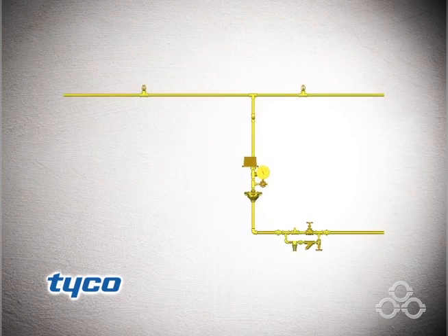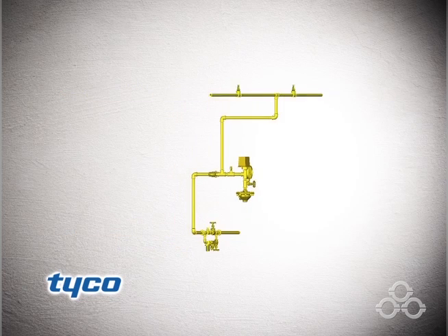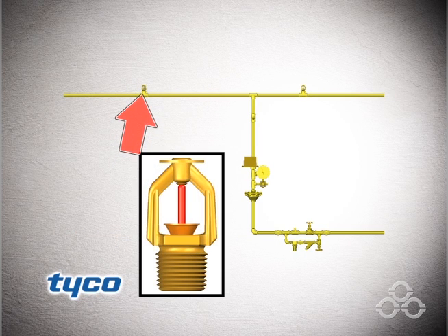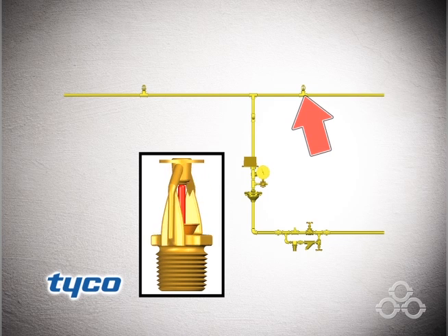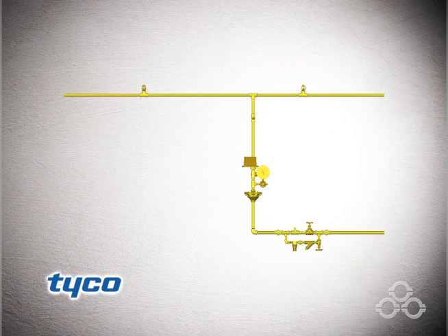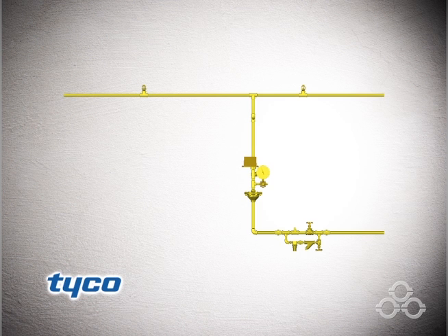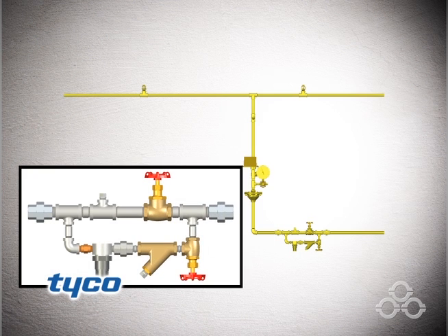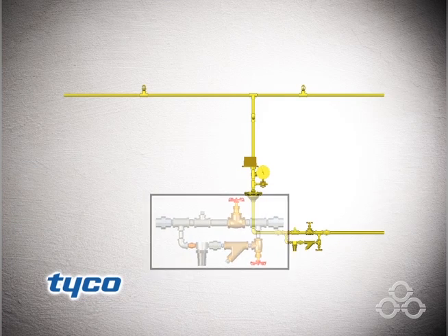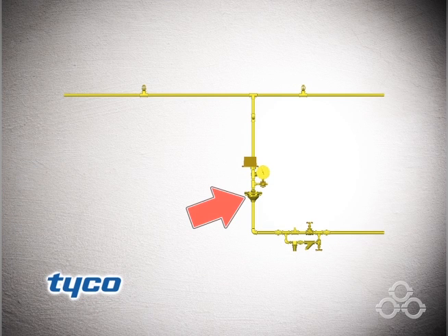The actuation system is shown here in yellow. The dry pilot actuation system is equipped with fire detection dry pilot devices, such as the Model FTR-1 fixed temperature release or automatic sprinklers. These are pressurized by air through an optional Model AMD-1 air maintenance device and the pilot port of the Model DP-1 dry pilot actuator.